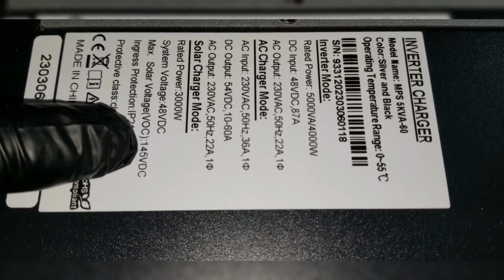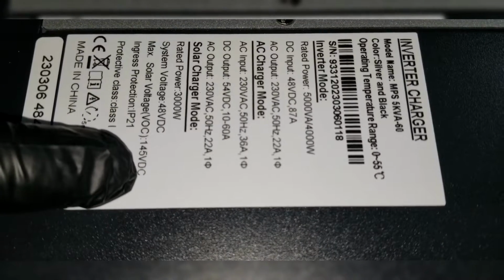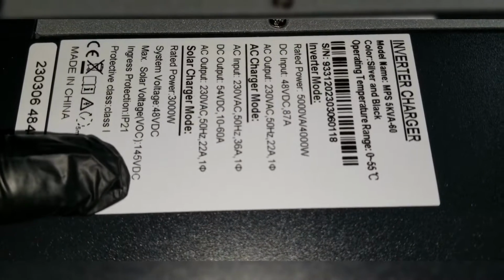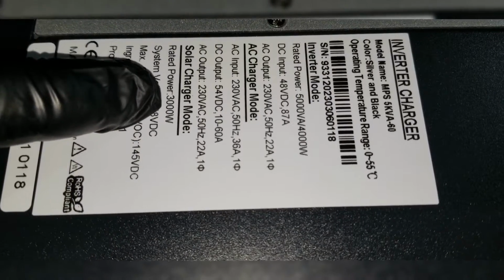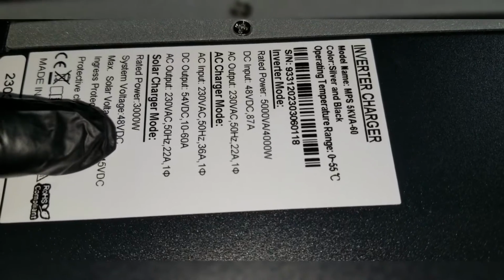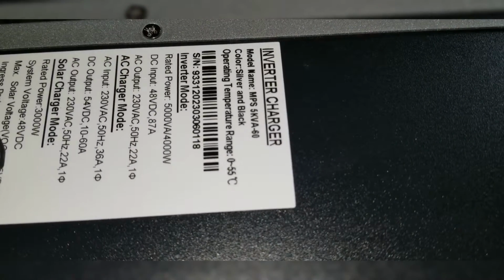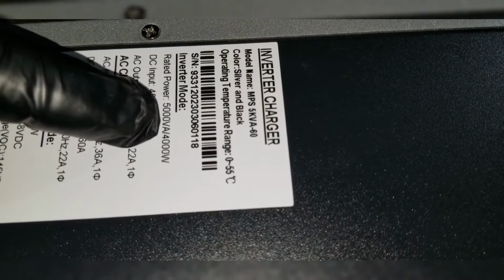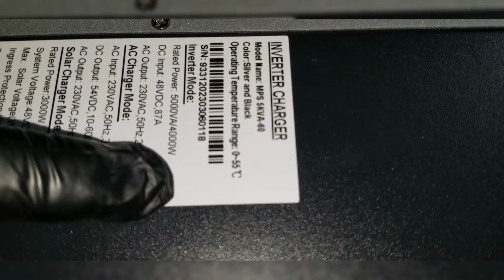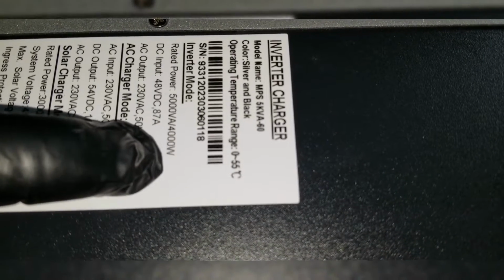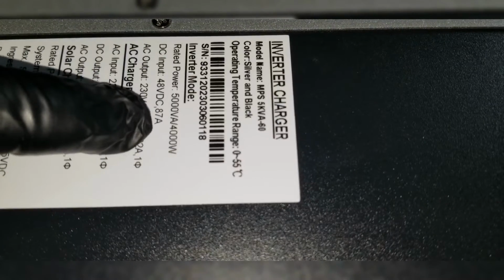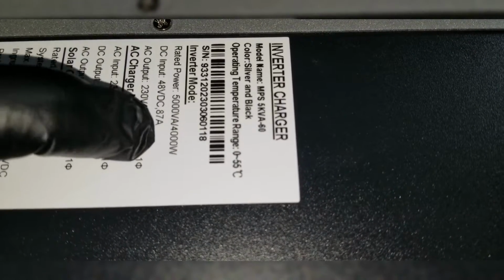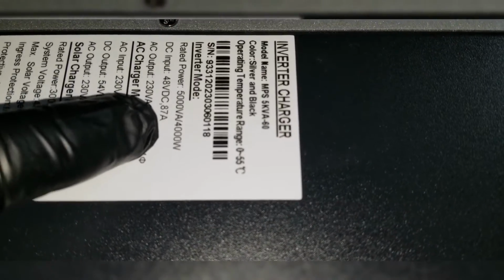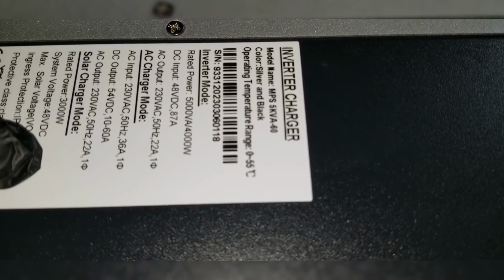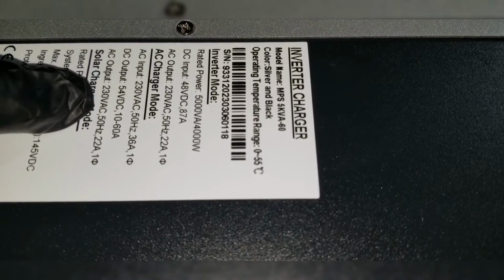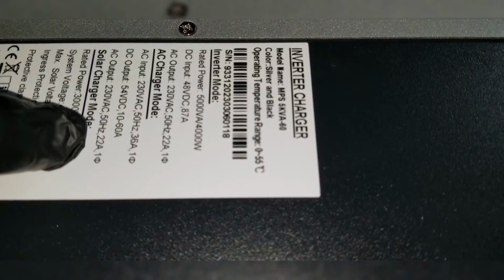The solar DC open circuit is 150 volts DC. The rated power, which is the charge, is 3000 watts. The rated output is 5000 VA, volt-amp, equivalent to about 4000 watts. You can use the input for DC, like your battery, and it requires about an 87 amp battery to run this. It's 230 volts, 50 hertz, 22 amps.